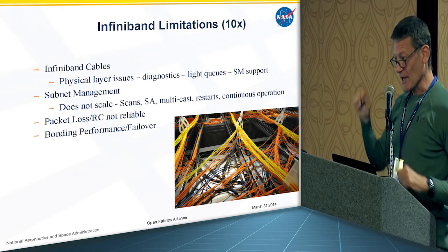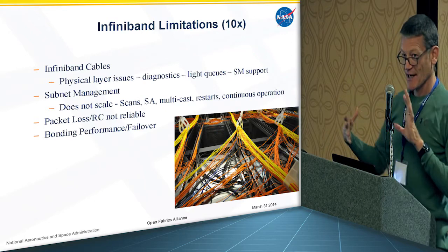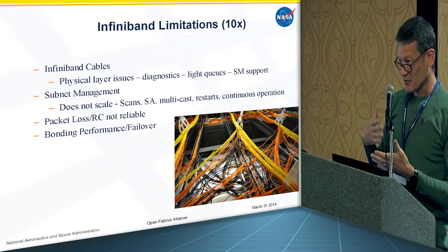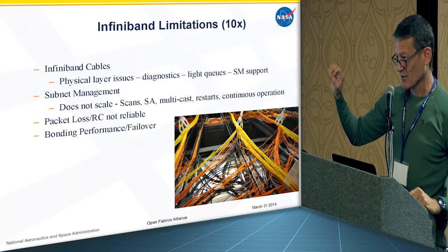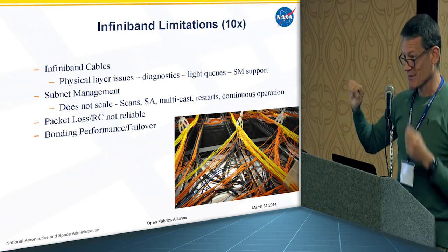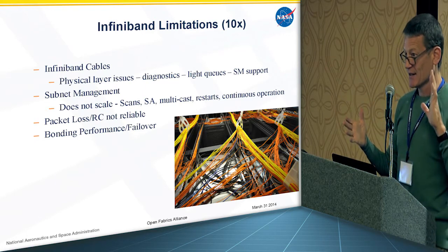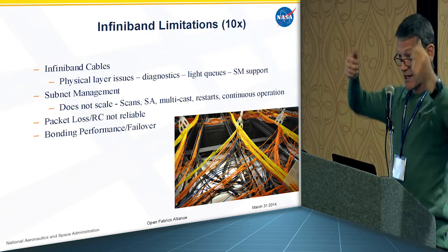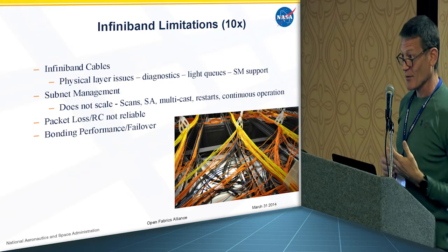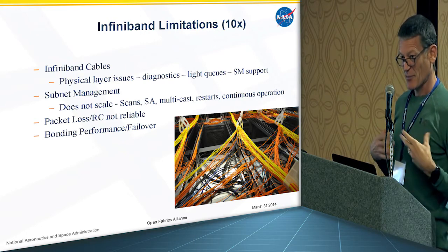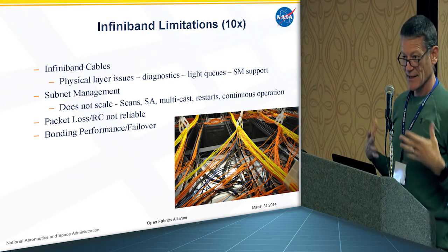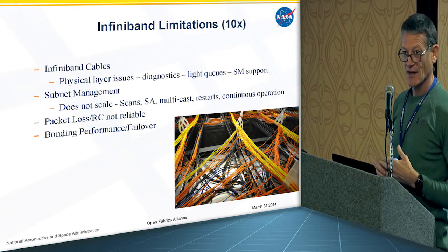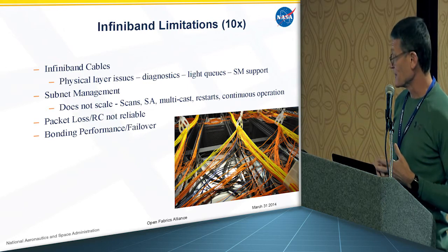It's very complicated, or just cumbersome, to map GUIDs and port numbers to physical location on the floor, and to get that right every time. And sometimes you make mistakes. It's late. Guys that have been doing this for years go in there and plug a wrong cable, pull a wrong cable, and cause a problem. So just the practical management of it is something that needs work. Human interface issues cause failures, and it can be improved.